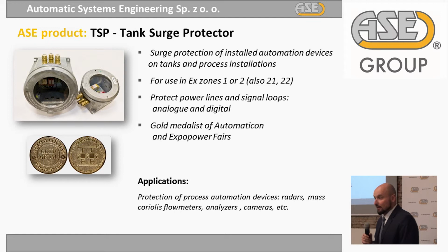It's very important to install the protectors as close to the protected device as possible. Normally we take this equipment somewhere far, to the safety zone. This solution gives us the possibility to install it directly on the tank, very close to the expensive radar, or very close to the Coriolis flow meter, also very expensive. So we can install the protectors very close to the protected device inside the Ex zone.